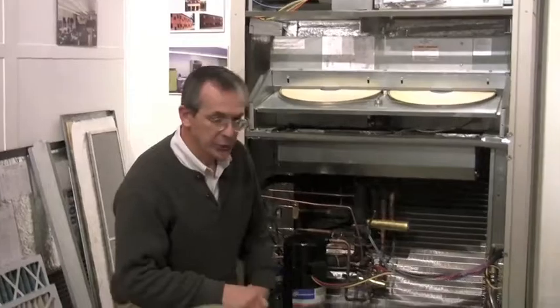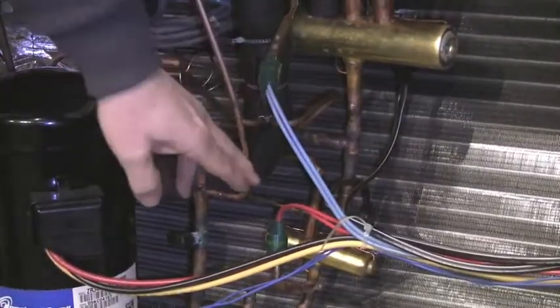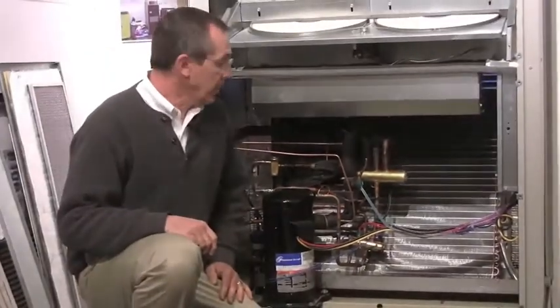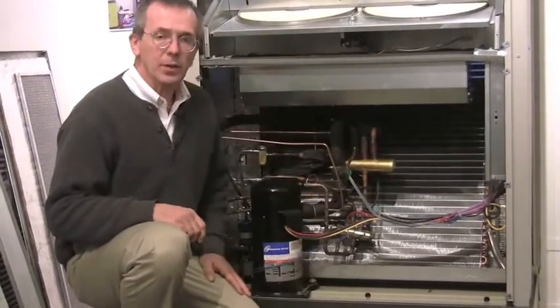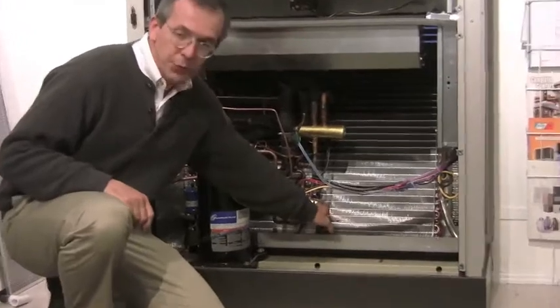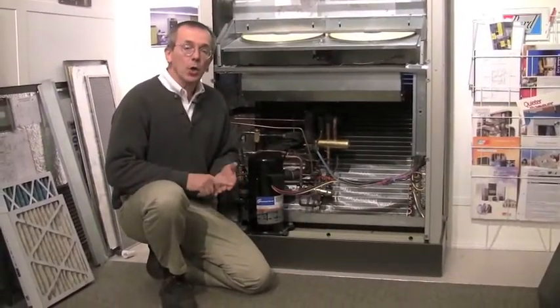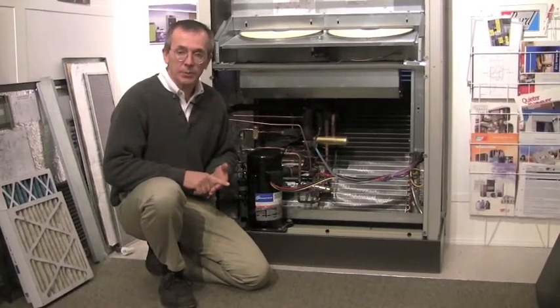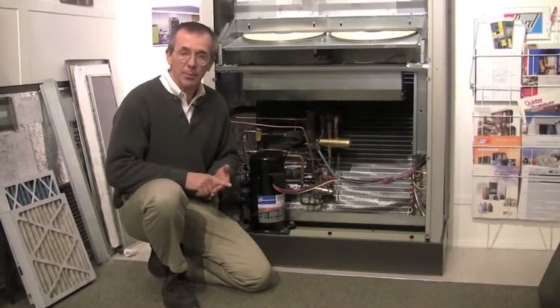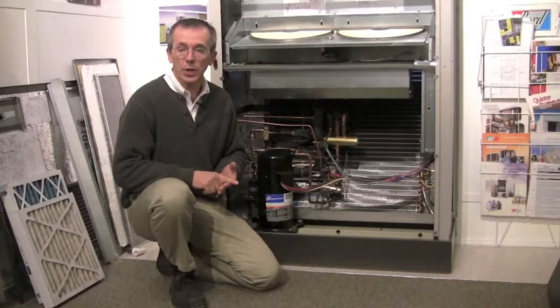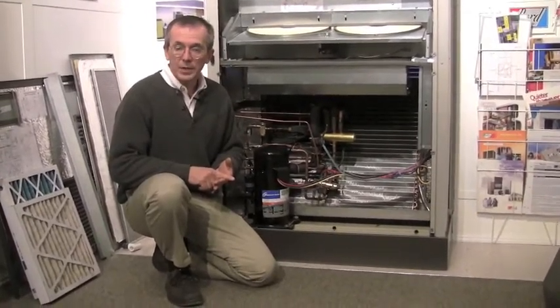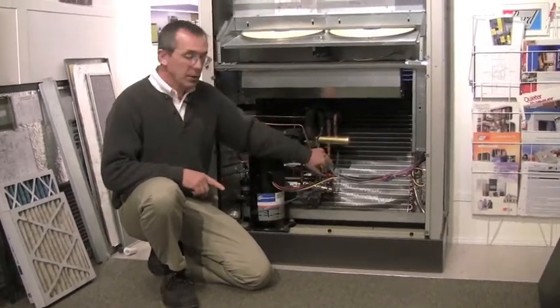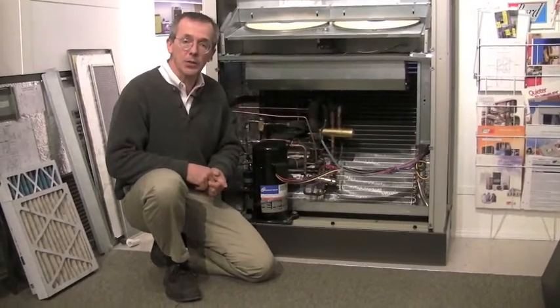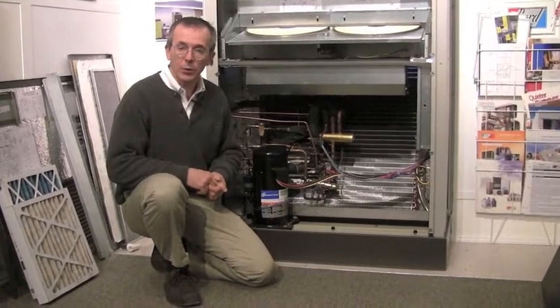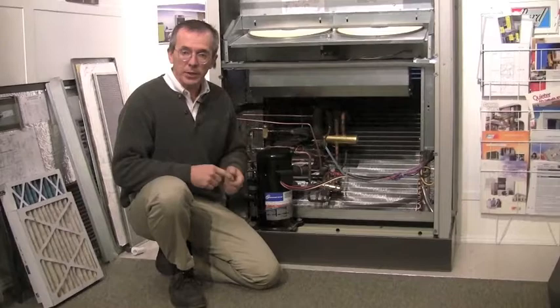Earlier we talked about the high and low pressure switch on the unit. Low pressure switch, high pressure switch. Again, this is a 3-ton heat pump, a reversing valve, and also we talked about dehumidification. This is the 3-way dehumidification valve. Let me say just a little bit more about dehumidification. Cooling takes precedence over dehumidification. So if the thermostat is calling for cooling and the humidistat part says that you need to dehumidify, the cooling will continue until the thermostat is satisfied. Once that happens, the blower will go to 3/4 speed, the valve will switch, and it will put hot gas up to the hot gas coil. So you still have a cold coil, you have a reheat coil, the air slows down, and you start the dehumidification process.